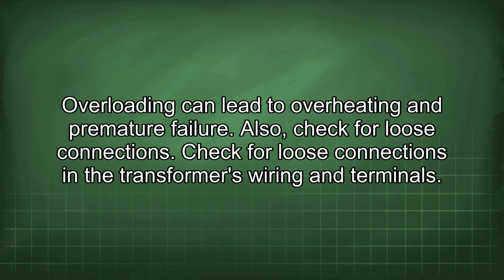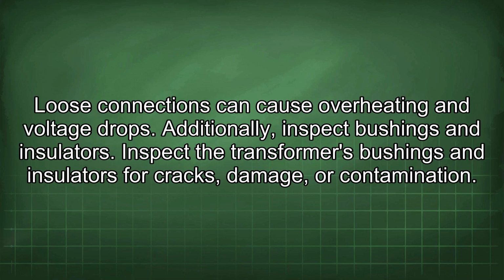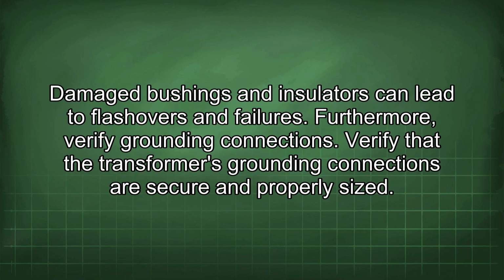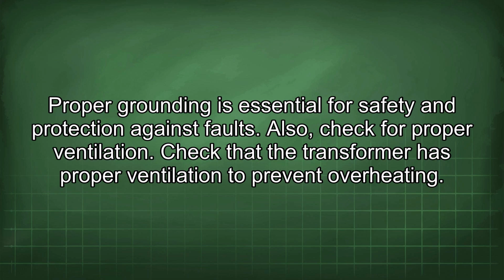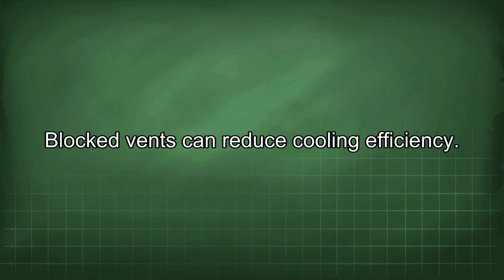Also, check for loose connections. Check for loose connections in the transformer's wiring and terminals. Loose connections can cause overheating and voltage drops. Additionally, inspect bushings and insulators. Inspect the transformer's bushings and insulators for cracks, damage, or contamination. Damaged bushings and insulators can lead to flashovers and failures. Furthermore, verify grounding connections. Verify that the transformer's grounding connections are secure and properly sized. Proper grounding is essential for safety and protection against faults. Also, check for proper ventilation. Check that the transformer has proper ventilation to prevent overheating. Blocked vents can reduce cooling efficiency.